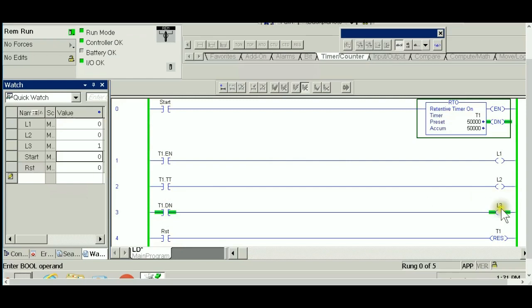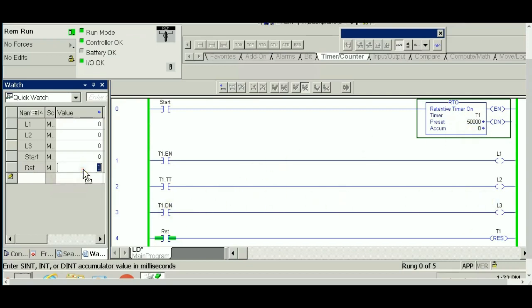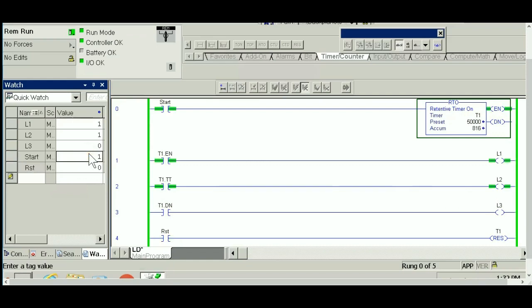To reset this thing using my input, I'm going to activate the RST input. This is true, it triggers a reset instruction, and what it does is get the accumulator back to zero. The done bit goes to zero and everything resets. Right now if I hit the start again, the timer will start accumulating time again, and that's the RTO.